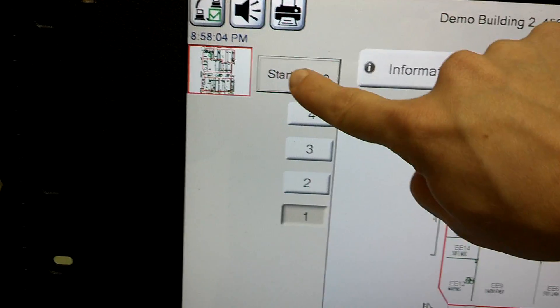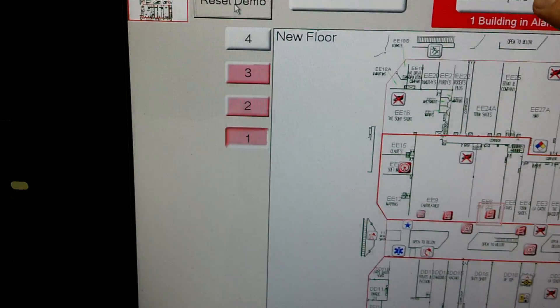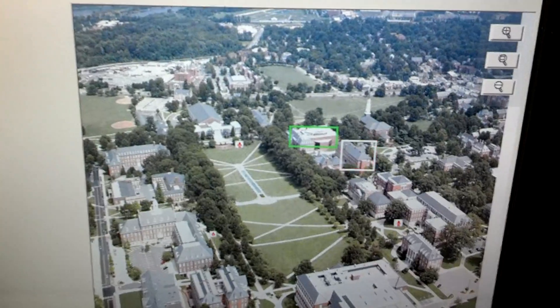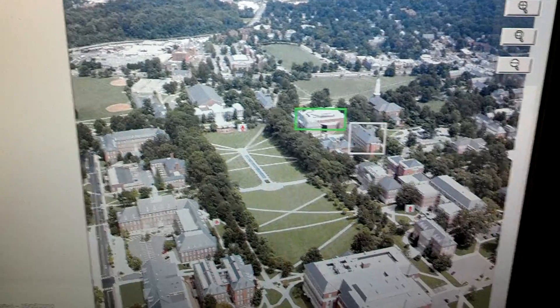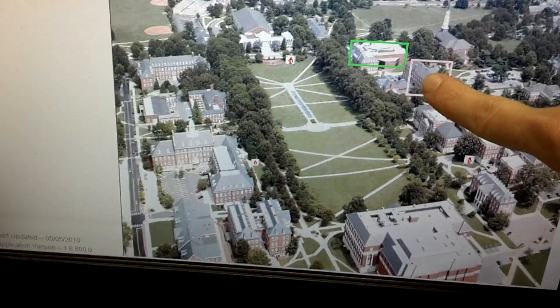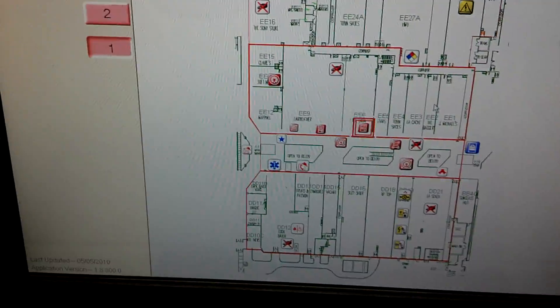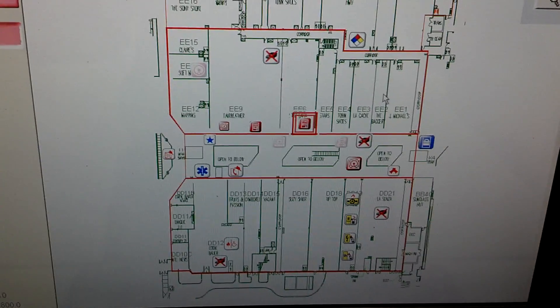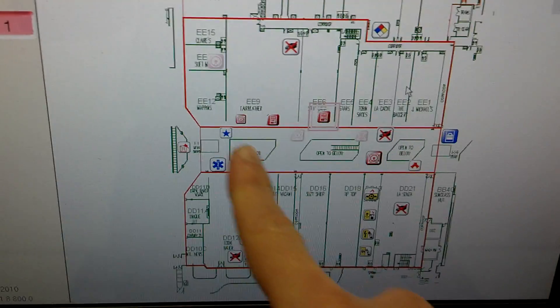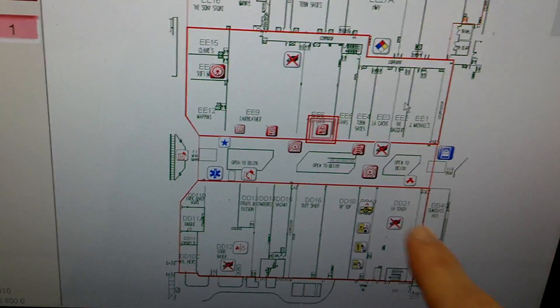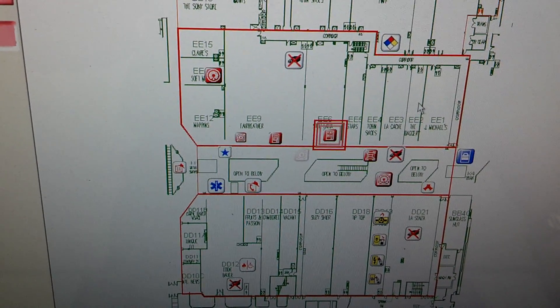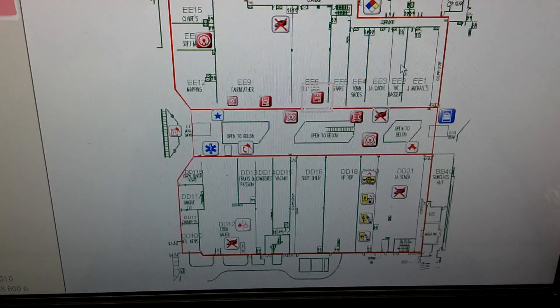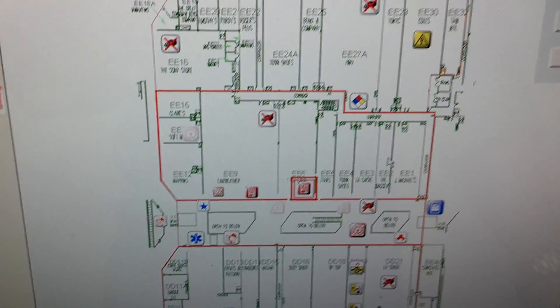When there's an alarm and you're on the campus view, that green square will start flashing red, showing you where the alarm is on the network so you can go directly into it. Once you're in here, all the devices associated with active alarms will light up. You can see them flashing, and the most current device in alarm that hasn't been acknowledged yet will be surrounded by flashing red squares — making it easy to see right off the bat where the device is located.